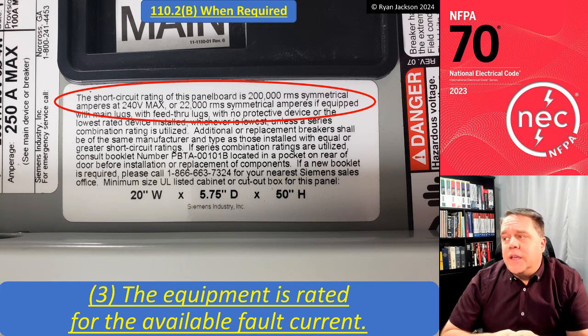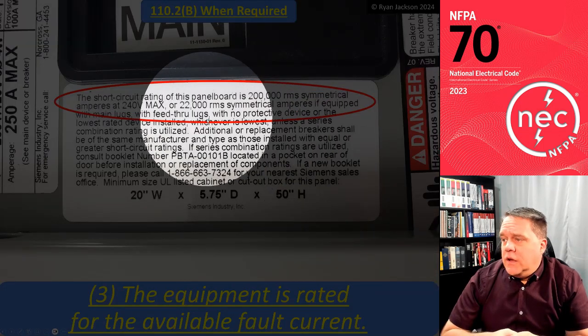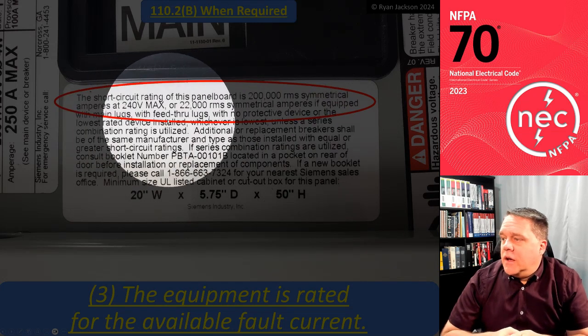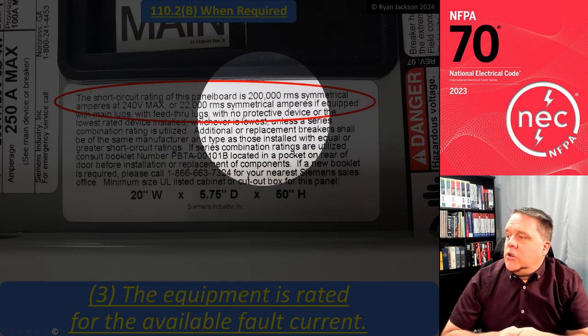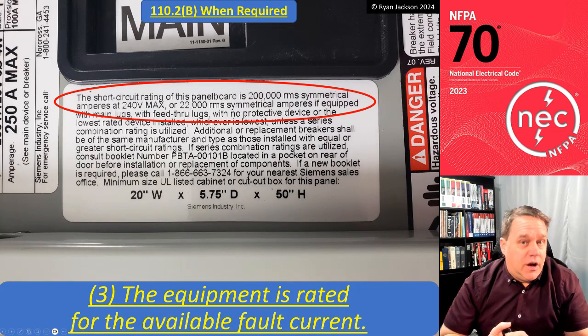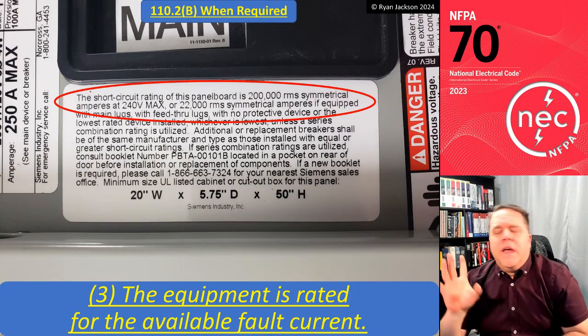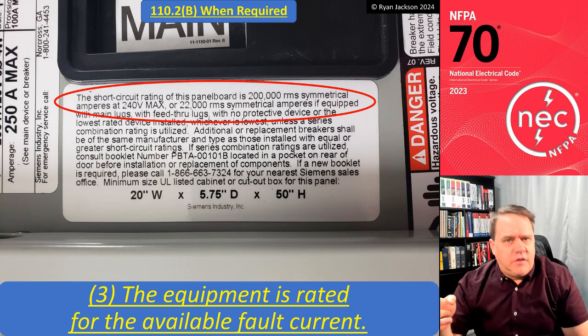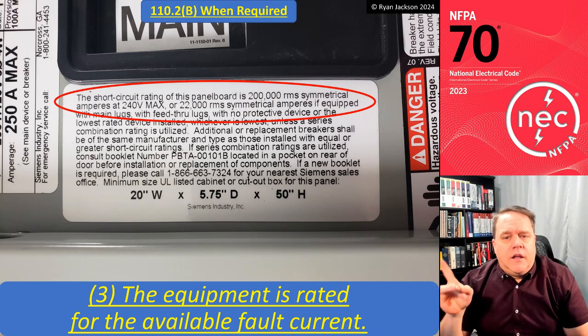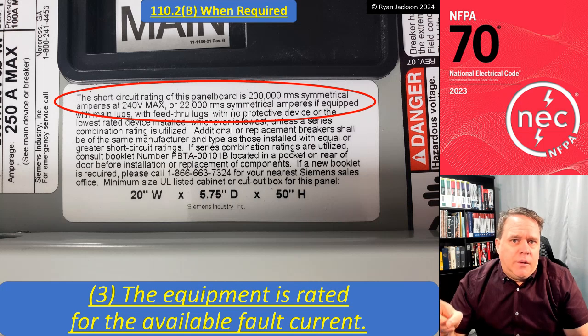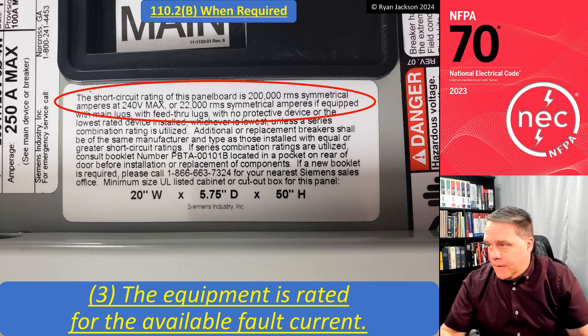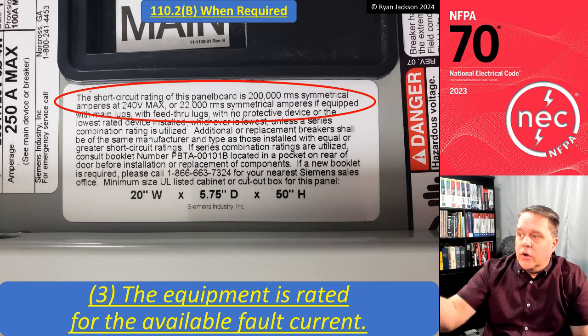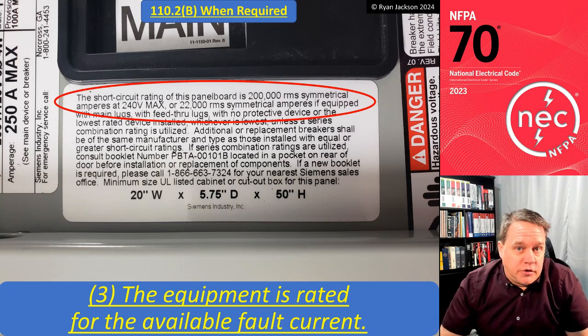But if I keep on reading it, it's only good for 22,000 if it's equipped with main lugs or feed-through lugs and no overcurrent device installed upstream of it. Okay, so if this was the service disconnect, for example, it does not have a 200,000 amp interrupting or short circuit current rating. It only has a 22,000 amp short circuit current rating.